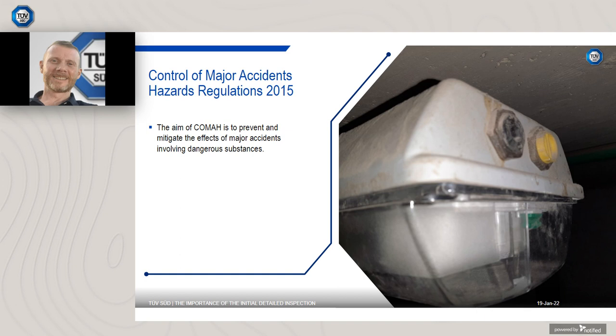The light fitting in the image had one certified plug fitted. The yellow plug is a shipping plug. It confers no protection in line with the certification for the fitting. The installer went to the trouble of fitting one plug, yet left the shipping stop and spare entry hole. The light was never inspected after the install. The factory were unaware of the requirements or functions of the type of Ex protection conferred by the light. They relied on an installer who did not possess the relevant knowledge of installation standards.